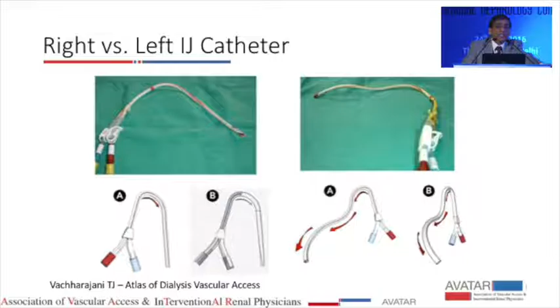Now, for catheter performance, it's not just the tip design that is important. There are other factors, patient factors and the operator factors, that are equally important. So just evaluating the tip design may not give us the correct answer to this question. Now, tip design definitely can affect the flow. It can definitely affect the recirculation rate, whether it's in a straight connection or in a reverse connection, and whether it leads to higher incidence of clot formation.